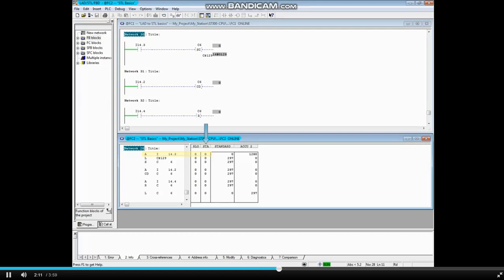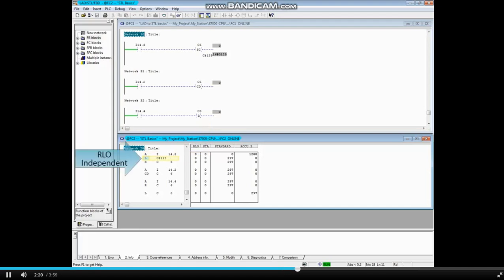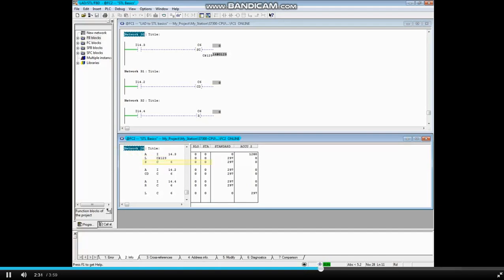When the status of i14.3 is true, the result of the logic for the AND instruction is true. The load command is RLO independent and always loads the count value 129 to accumulator 1. The set command, however, depends on RLO and transfers accumulator 1's value to counter 6 if the RLO is true.